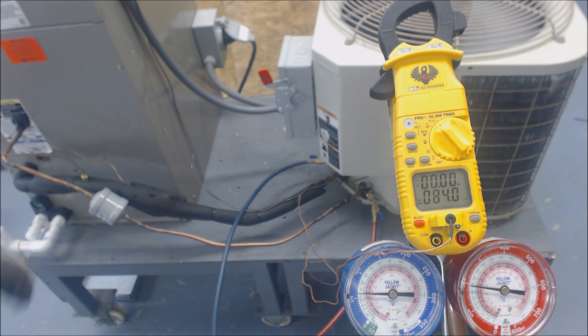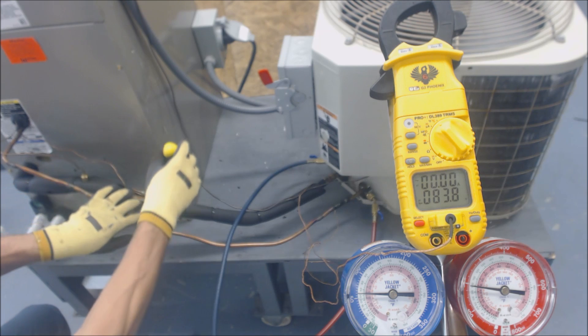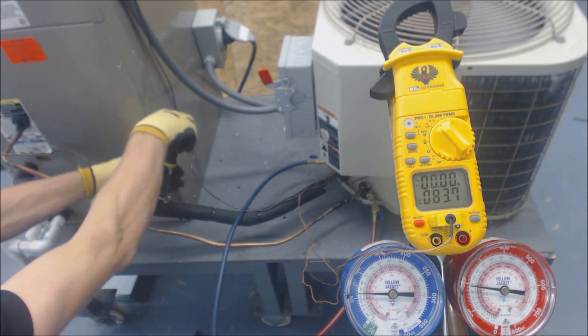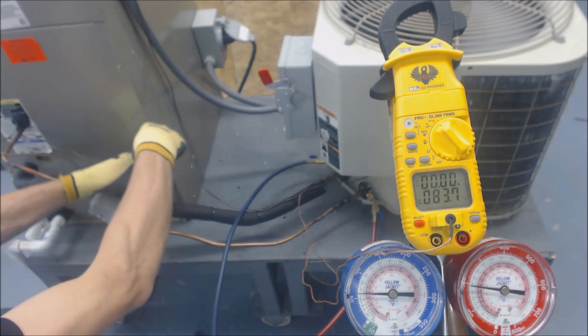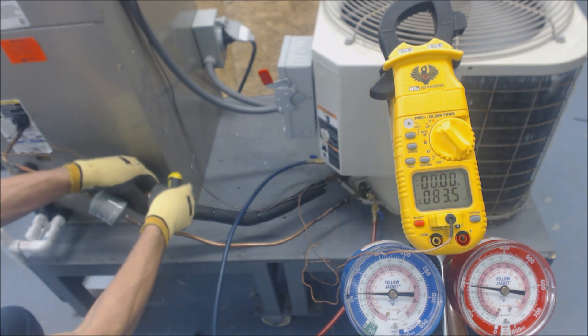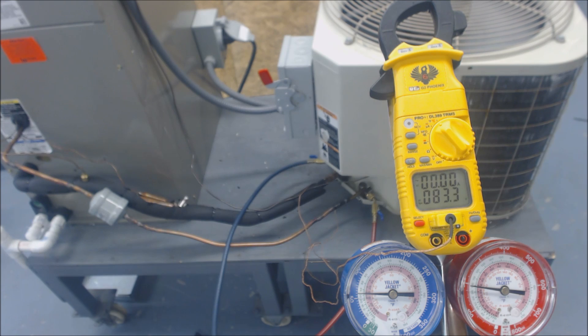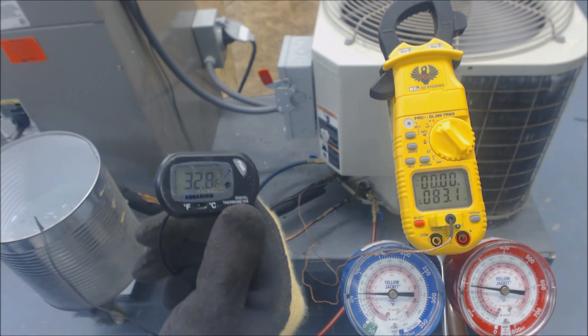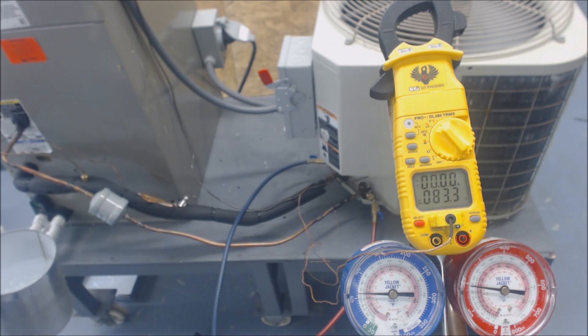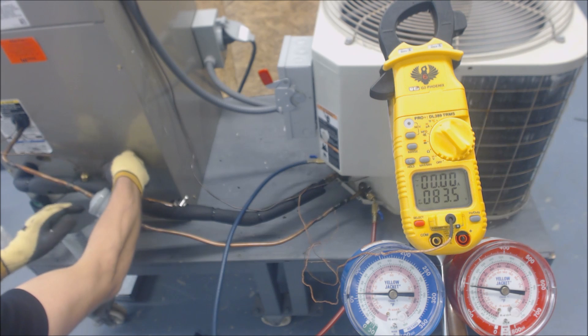Now we're going to play around with this TXV bulb. We're going to show as if the TXV bulb has lost the refrigerant. If the TXV bulb loses its refrigerant charge, it will not be able to apply force onto the head of the TXV. We're going to take the TXV bulb out and we're going to be putting it in ice water.